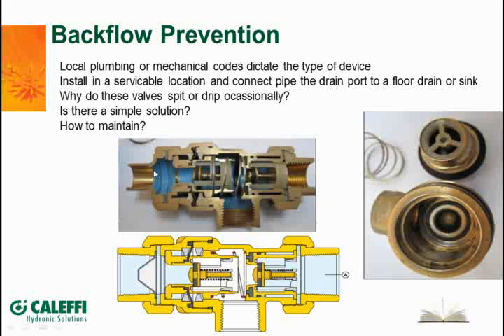Now, we are protecting these now. They do have a little strainer that we built into this little tail piece here. It is removable, and you can clean it out. It's a very small capacity, obviously, because it's the diameter of this pipe here, so they can plug up pretty easily. If you're hooking this up to an old galvanized water system that has a lot of rust or scale or debris in it, you can plug that strainer up, and you're not going to get much flow through it. And your fill valve, of course, isn't going to fill at that 5-gallon-a-minute rate if the strainer in the backflow preventer is plugged up. So one of the things you want to check when you go to a troubleshooting job is to just take this apart and make sure that the strainer is cleaned out. Some people use it once and discard it, and that's another way of making sure they don't plug up and cause a problem.